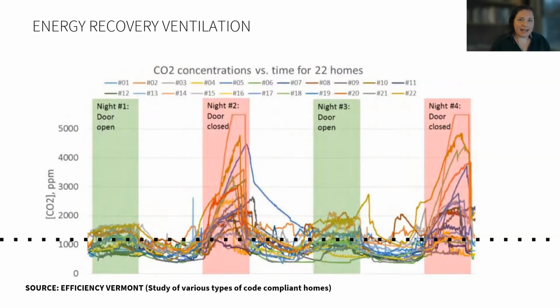Unless we are providing dedicated fresh air that is balanced between supply and exhaust, the building is not achieving real air changes. It's difficult to measure this, but there are a number of studies available to demonstrate it. There is a much higher risk for condensation issues and high CO2 levels, or a buildup of many other toxins. Building codes are progressing towards requiring intentionally supplying fresh air to all habitable spaces, just as sprinklers became baseline not too long ago. In fact, in the International Energy Conservation Code of 2021, ERVs are required in multifamily buildings. Ventilation can be considered a life safety issue in many ways if you consider the implications on health.